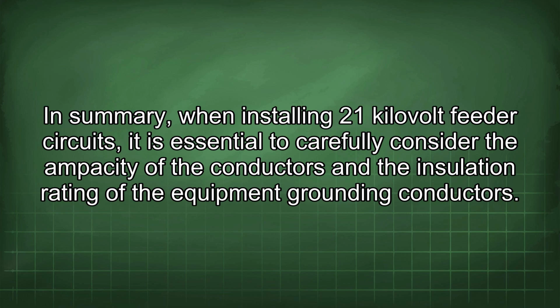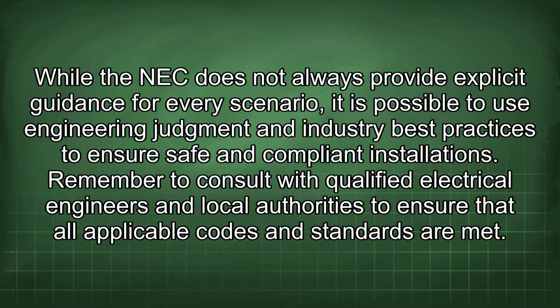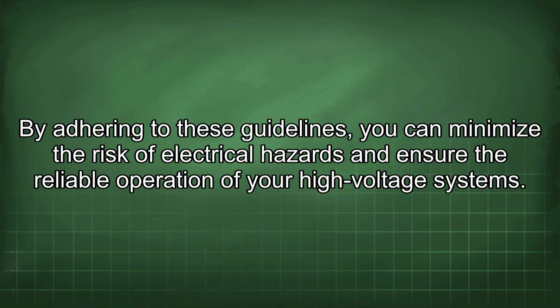In summary, when installing 21 kV feeder circuits, it is essential to carefully consider the ampacity of the conductors and the insulation rating of the equipment grounding conductors. While the NEC does not always provide explicit guidance for every scenario, it is possible to use engineering judgment and industry best practices to ensure safe and compliant installations. Remember to consult with qualified electrical engineers and local authorities to ensure that all applicable codes and standards are met. By adhering to these guidelines, you can minimize the risk of electrical hazards and ensure the reliable operation of your high voltage systems.